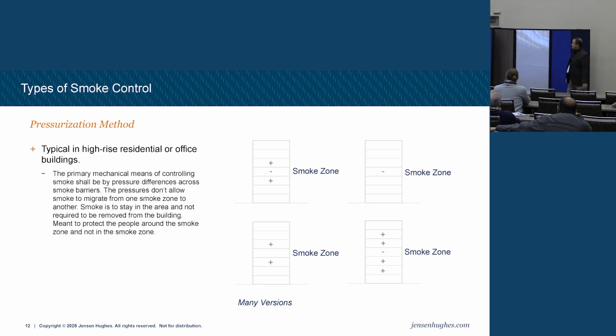All right, the pressurization method. Legacy, this was very, very common. It's not as common in the automatic world anymore. California, it's still pretty common. It's also been called sandwich pressurization. So the idea would be, if I have a fire on this floor here, I negatively pressurize that, so all my air handlers go to a negative exhaust mode, and the floor above and the floor below go to a positive pressure mode. The idea being, force that smoke to stay right there. Then I turn on the stairwell pressurization systems and I keep it out of my stairwells. That's the idea.